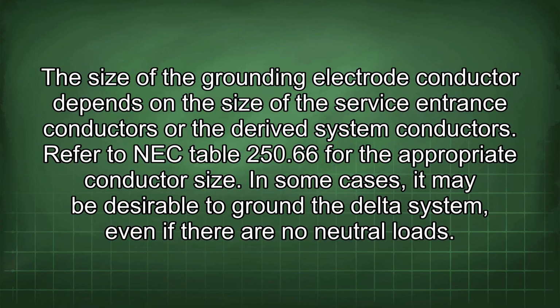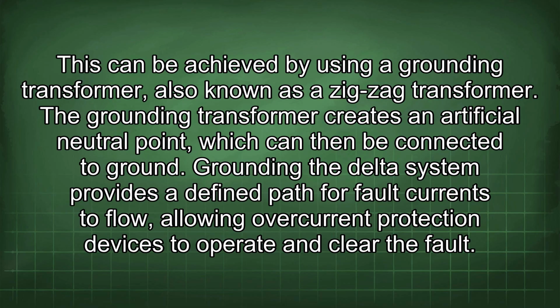Refer to NEC Table 250.66 for the appropriate conductor size. In some cases, it may be desirable to ground the delta system even if there are no neutral loads. This can be achieved by using a grounding transformer, also known as a zigzag transformer. The grounding transformer creates an artificial neutral point, which can then be connected to ground.